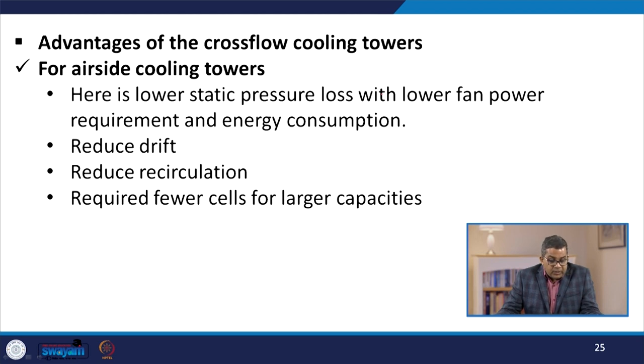Now, if we talk about the air side and discuss the advantages pertaining to the cross flow cooling tower, the main advantage is the lower static pressure loss with lower fan power requirement, and thereby the energy consumption is on the lower side. So, you may say that these are somewhat energy efficient. They also reduce the drift. They also reduce the chances of recirculation, and they require fewer cells for larger capacity. That is why they offer some sort of economy on the air side.